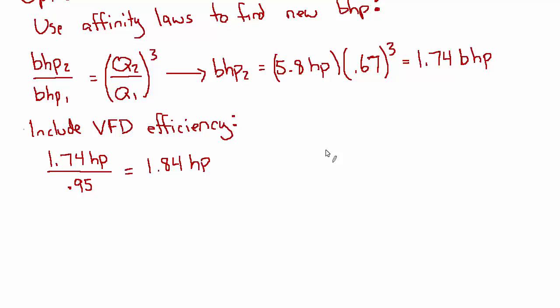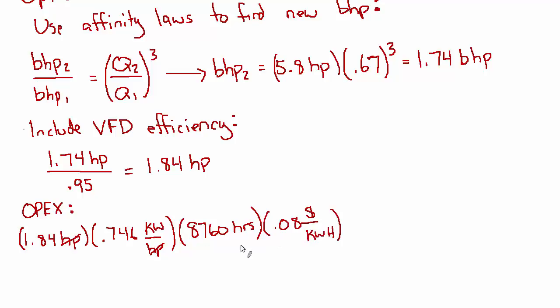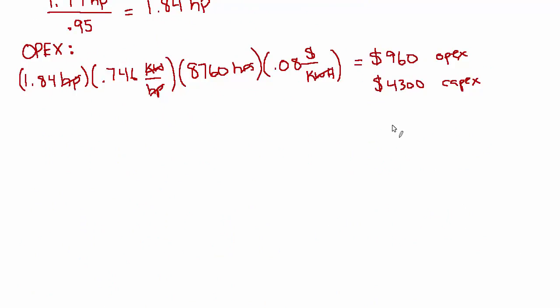So let's figure out what the operational cost of that will be for a year. We have the 1.84 horsepower times 0.746 kilowatts per horsepower times 8760 hours in a year. So now we're in kilowatt hours and then 8 cents per kilowatt hour. So kilowatt hour gets rid of all these and we're just left with dollars. So that's 960 OPEX. And then the capex we said was $4,300. So I'll just put that there so we have it all together. And that is the financial analysis for option one for the VFD.